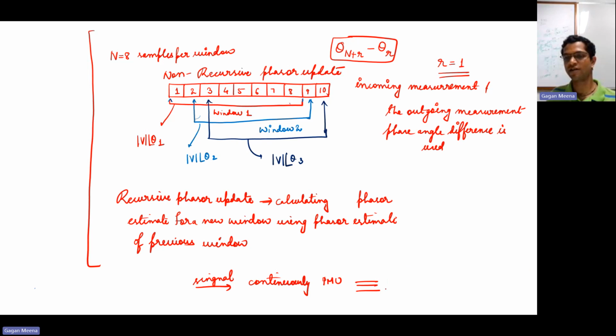How does fault detection happen? Suppose for each window, the difference between the phasor estimate of the previous and current window increases to a large value, and if it goes beyond a threshold, then we say there is a fault because current has increased too much. In normal operation, the current magnitude will remain the same. But in case of fault, there will be a sudden increase in current.